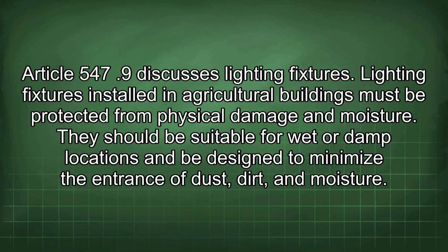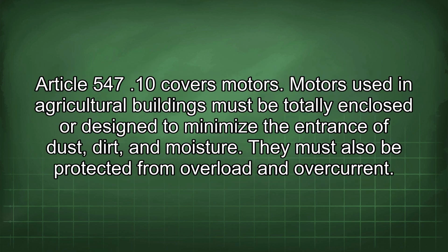Article 547(9) discusses lighting fixtures. Lighting fixtures installed in agricultural buildings must be protected from physical damage and moisture. They should be suitable for wet or damp locations and be designed to minimize the entrance of dust, dirt, and moisture. Article 547(10) covers motors. Motors used in agricultural buildings must be totally enclosed or designed to minimize the entrance of dust, dirt, and moisture. They must also be protected from overload and overcurrent.